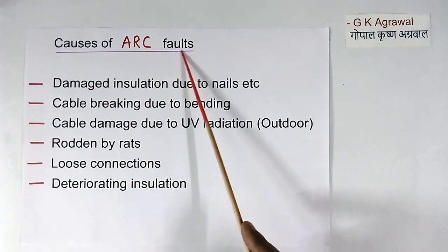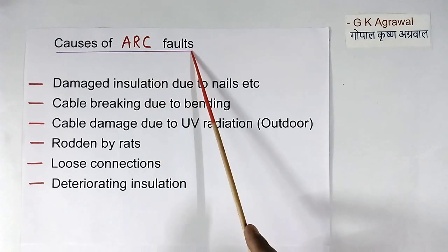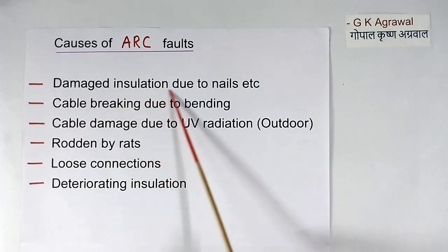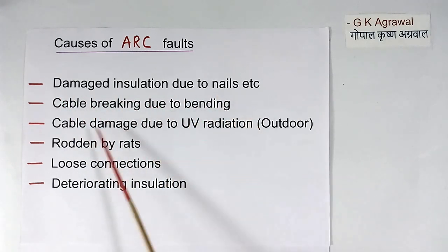Now causes of arc fault. This happens due to cut in insulation and wire. It may be due to damaged insulation, due to nails, cable breaking due to bending, cable damage due to UV radiation, cut by rats, loose connections. In this insulation quality will come down after using many years. So because of all these reasons, arc fault may be possible.